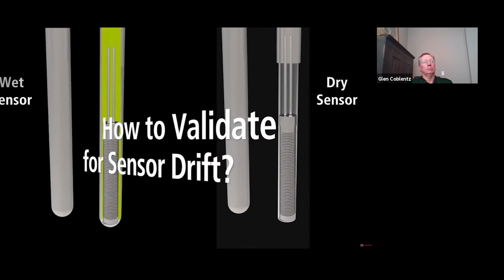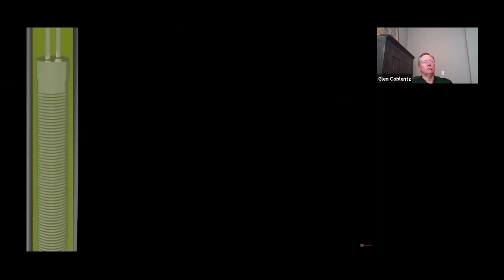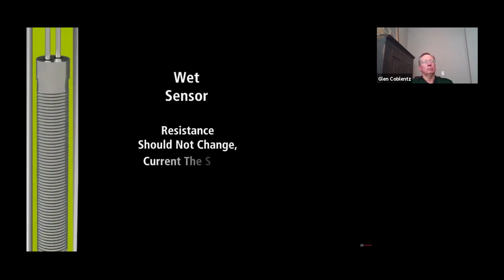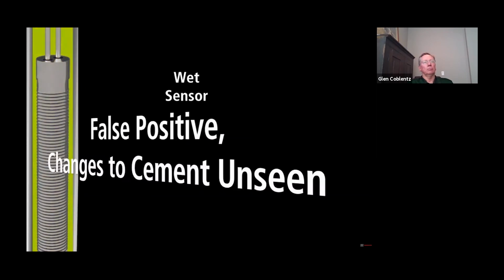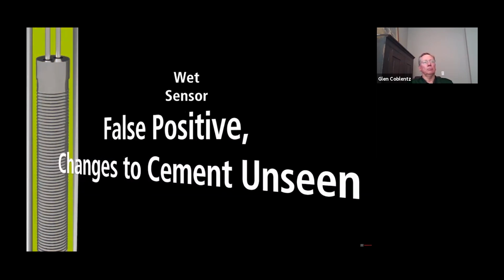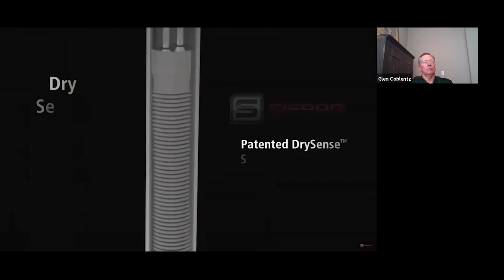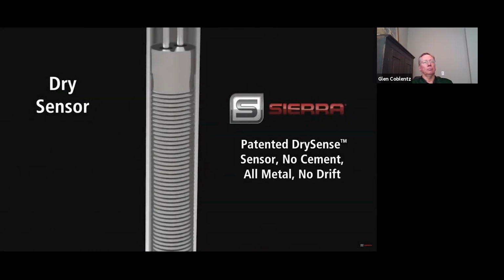to the very nature of its mechanical design? The resistance of the platinum wire shouldn't change, and the current running through the sensor might be the same, both of which would validate OK. This is a false positive, as the drift inherent in a wet sensor design would remain unseen. Sierra's DrySense all-metal no-drift sensor has a big advantage during in situ calibration validation. With Sierra's all-metal DrySense velocity sensor, you have the mechanical design confidence that there will be no drift and that in situ calibration validation is indeed actually valid.